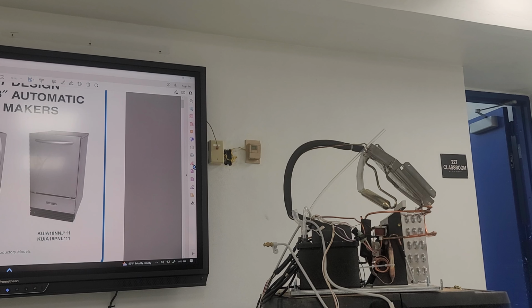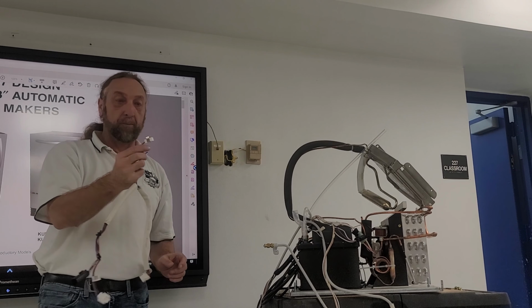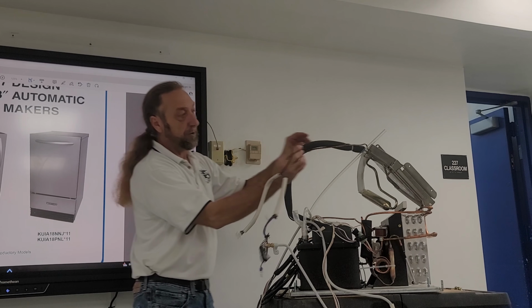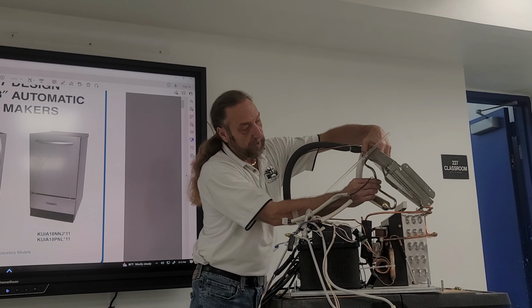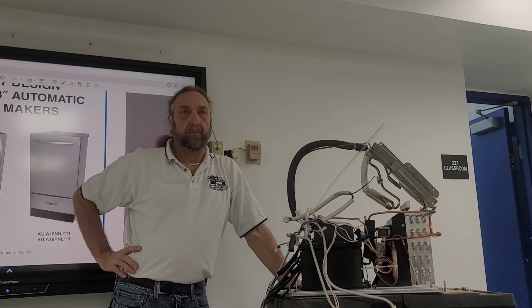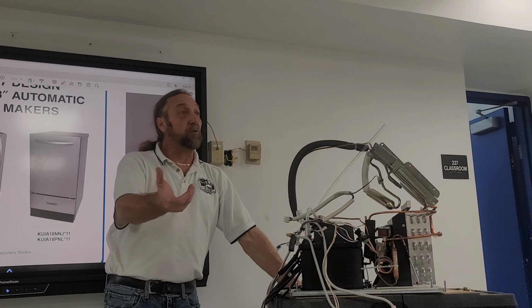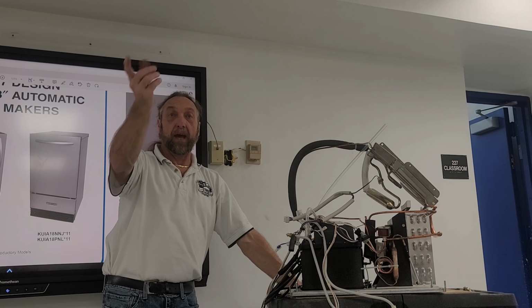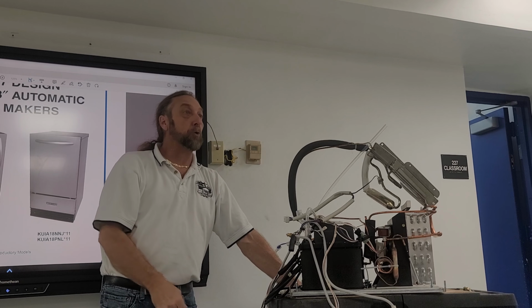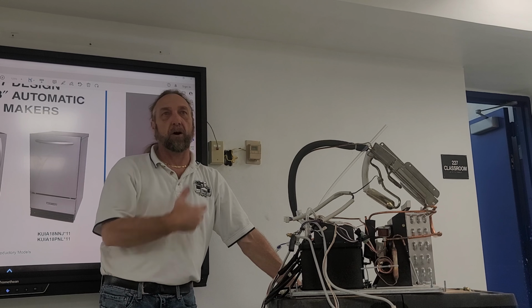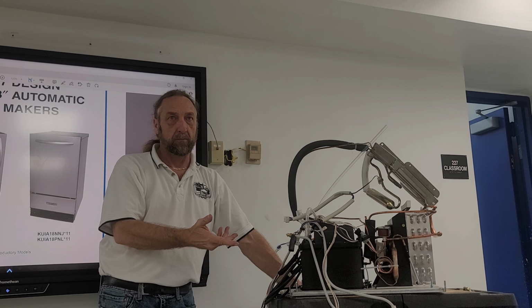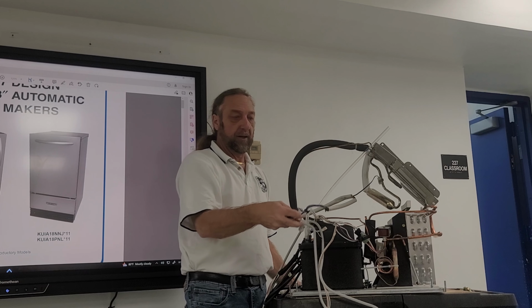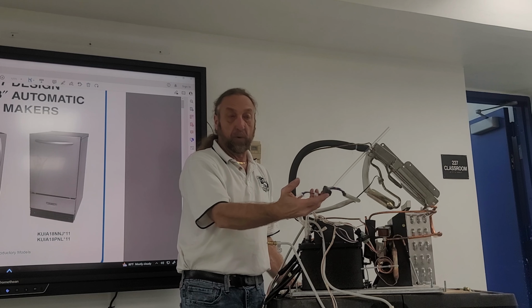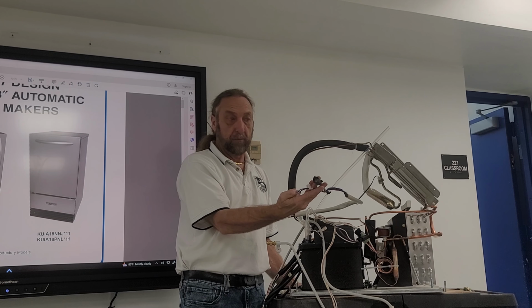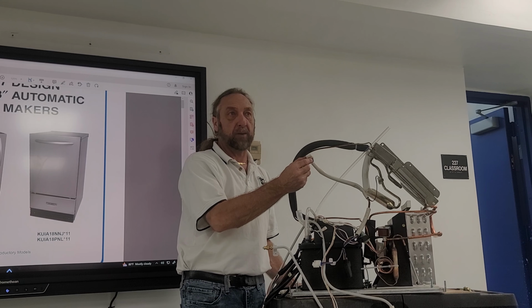Pause that for a second. Here. This is our evaporator thermistor. That evaporator thermistor clips onto this line right there. So if you can't see it, take your phone or something, take a picture with a camera so you can see where it is. Don't just pull it off and say, man, I don't know where I took it off. I need to put the new one on. Okay, so this here is our connections to our pumps, our recirculation, our drain pump. And then this one connects up to the main board.